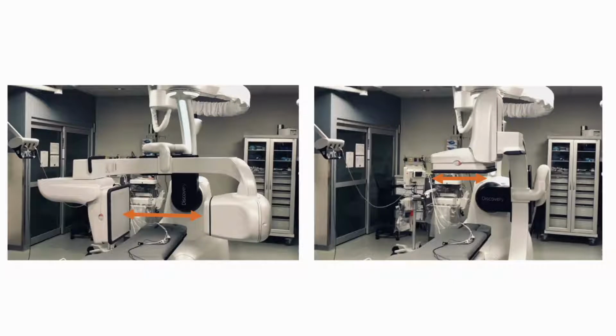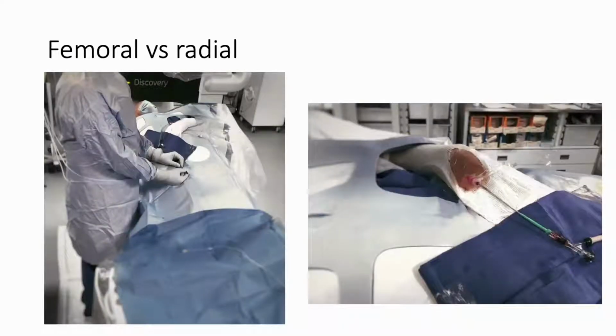And the other thing that I hope is apparent from this picture is that because the C-arm is offset to the left of the source and the detector, you can push the table in the cranial direction to easily allow for cone beam all the way down in the low pelvis, for example, for your prostate artery embolization cases. So, gone are the days of me having to supervise the patient's positioning on the table before the prep and drape, saying, hey, we've got to move the patient towards the head of the bed, or we've got to offset the patient so the liver is centered on the table. I don't have to do that anymore to ensure successful cone beam CTs.